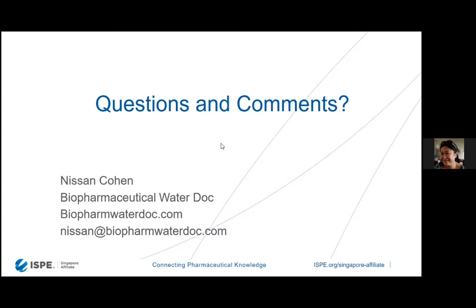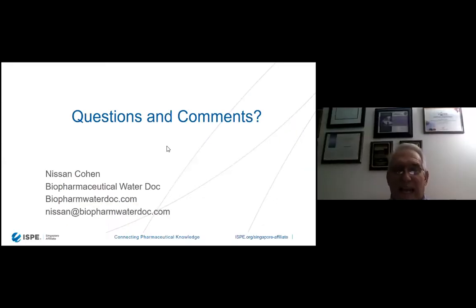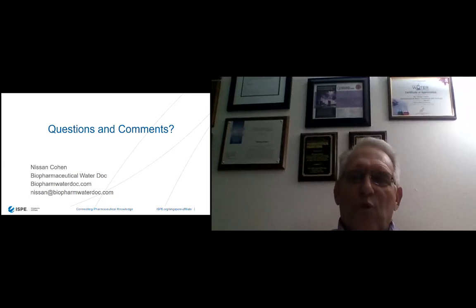The first question comes from Stephen Amadeus, and he asks, does the rouging phenomenon also happen in cool looping or ambient temperature, other than hot looping? The answer is yes. Rouge will happen in any water. Think about the Titanic sitting in less than 4 degrees Celsius water at the bottom of the Atlantic Ocean. It's corroding. It just corrodes at a lower rate. So rouge in ambient systems may take 10, 12 years to get to the same rouging level as a hot water system in 6 months, or a year.